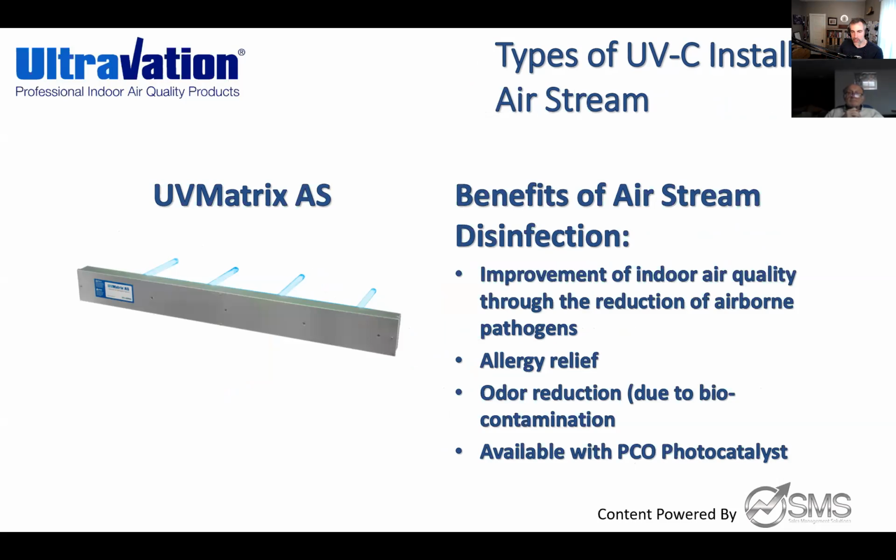So this is our airstream design to put on a supply duct. And again, all the components will be outside of the ductwork. The only thing you're cutting in is to get the bulbs into the ductwork, and that's it. We keep everything outside of the ductwork, so we're not restricting airflow, impacting the pressure that you've already designed the system for. And again, all of these components we're dealing with reducing allergies, reducing airborne viruses, disinfecting the air. Again, this design here, we can also add on the PCO that we reviewed earlier residentially. So if we need an application where somebody wants to get a photocatalytic upgrade added on, we could do that on this model as well.